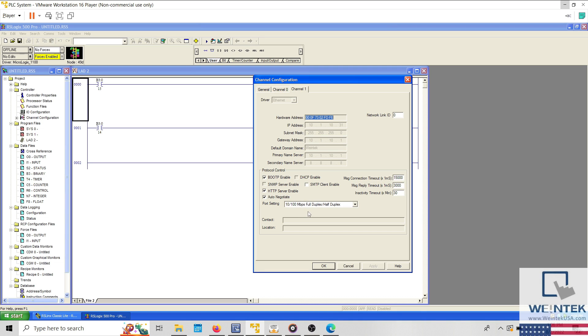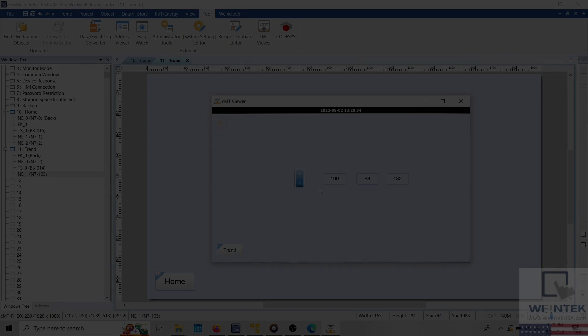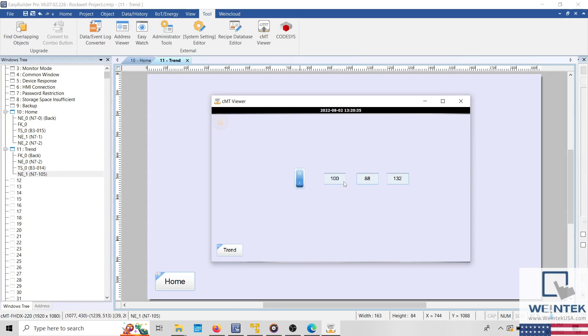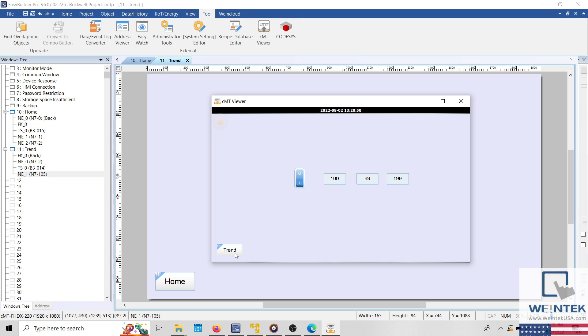So what might be causing this communication issue? To find out, let's consider the following. The HMI appears to display several objects that are addressed to and read from the PLC. This indicates that the HMI can communicate with certain registers in the PLC. The device no response message is only displayed on the trend window. This tells us that there is some object that is local to this window, like a bit lamp that cannot communicate with a register in the PLC.